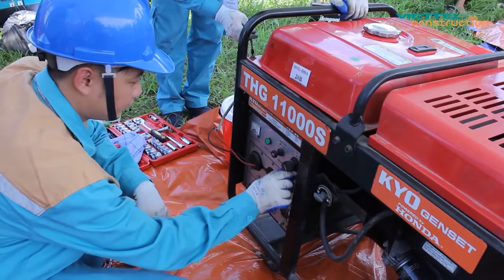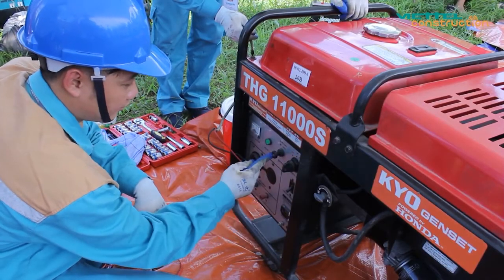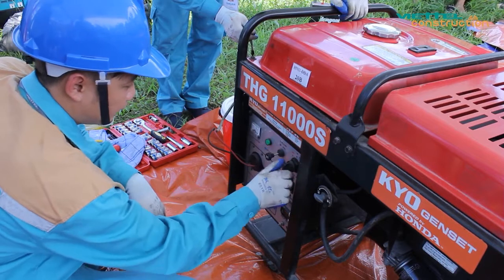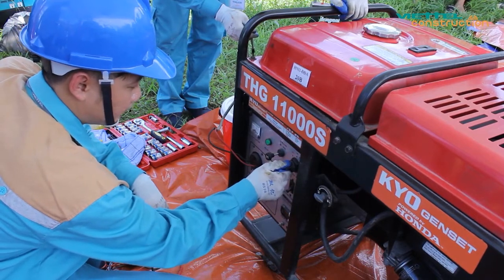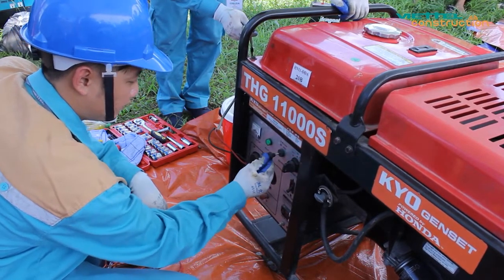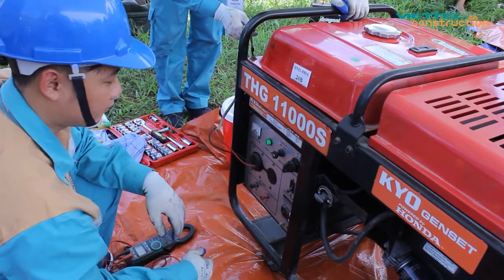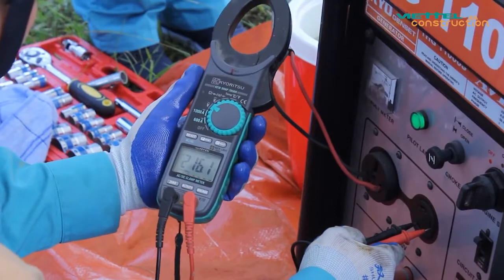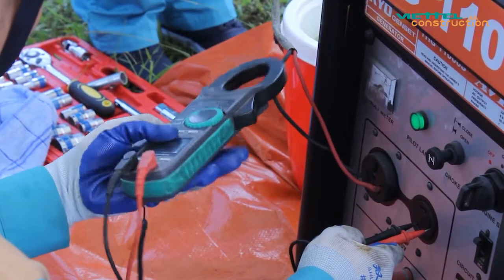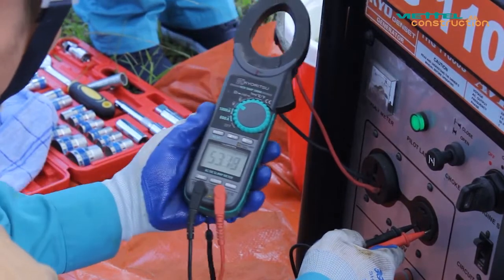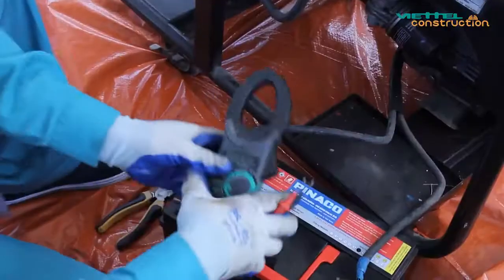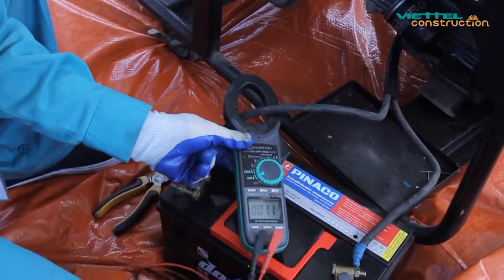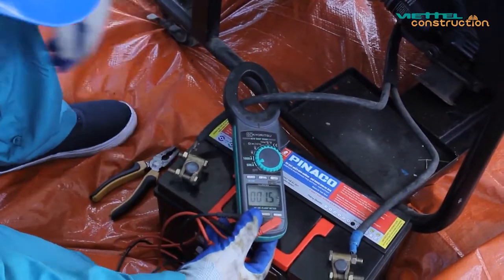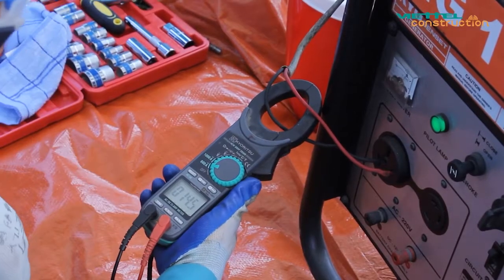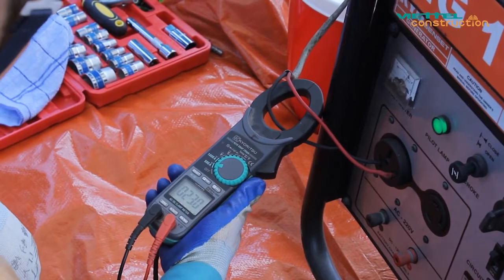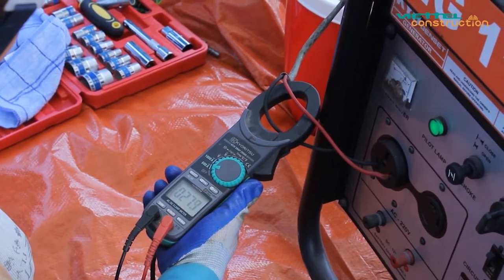After checking the guaranteed conditions to ensure operation, start the generator and measure it in the no load mode and in the loaded mode, according to the following parameters on the controller: voltage equal to 220/380 volts plus or minus 2.5%, frequency equal to 50 Hz plus or minus 5%. Check the charging current of the battery, when there is no load and when there is a load of 50 to 80% of the machine capacity.